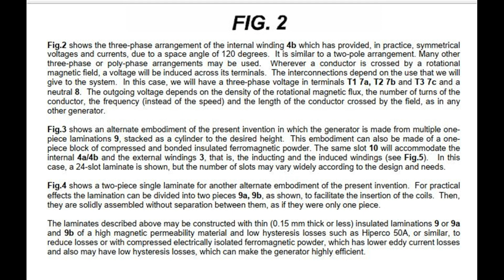In this case, a 24-slot laminate is shown, but the number of slots may vary widely according to the design and needs. Fig 4 shows a two-piece single laminate for another alternate embodiment of the present invention. For practical effects, the lamination can be divided into two pieces 9A, 9B, as shown, to facilitate the insertion of the coils. Then, they are solidly assembled without separation between them, as if they were only one piece.